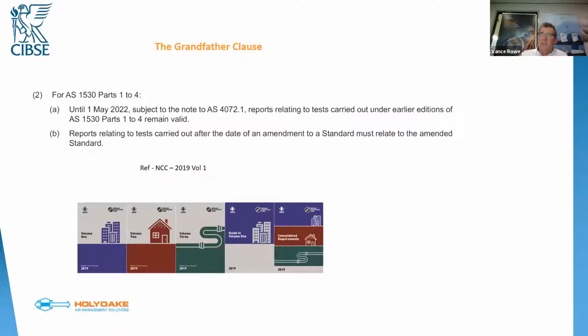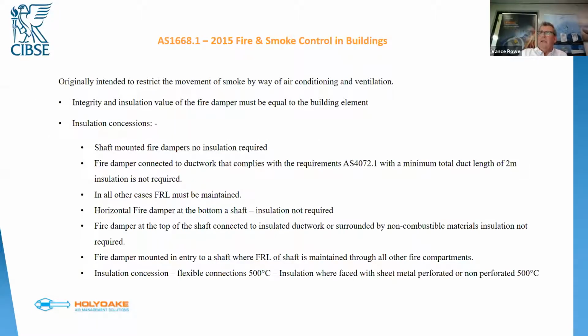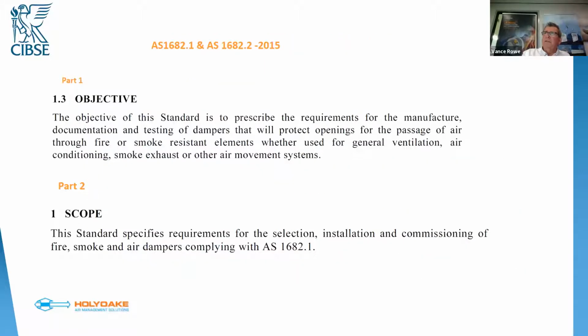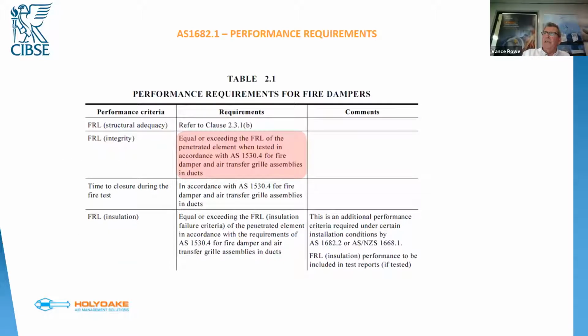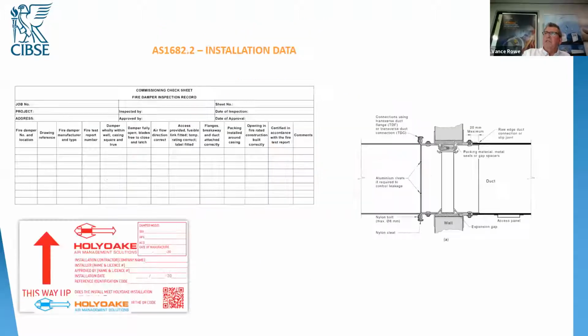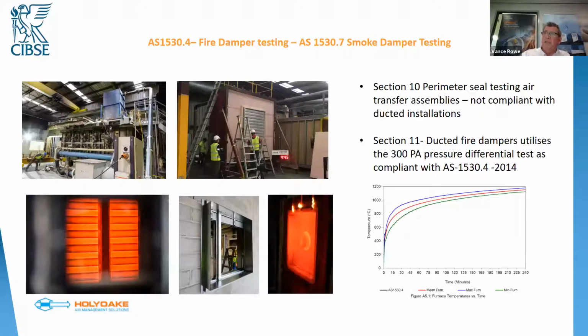Obviously, that's AS 1530.7. A little bit of information on the standards there. I'm actually going to rush through that and let everybody have a little read through that afterwards. But I would draw your attention to AS 1682.1 and the performance requirements for fire dampers and smoke dampers and fire smoke dampers. Also, air control dampers are listed in that standard.